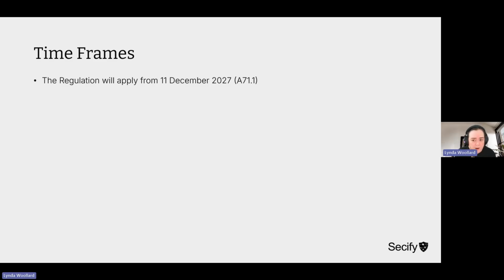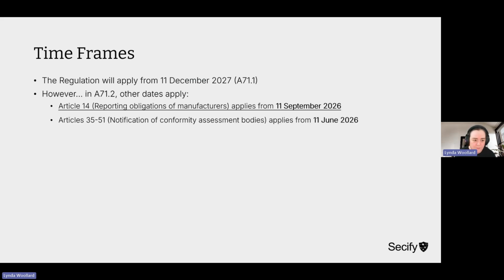When we talk about the timeframes, the regulation will apply from the 11th of December 2027. So we still have some time. However, in Article 71.2, other dates apply. If you're a manufacturer, your Article 14 reporting obligations start to apply from the 11th of September this year. So you have to essentially be ready to report actively exploited vulnerabilities or severe incidents.